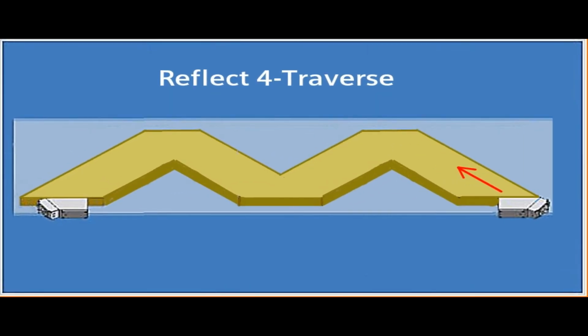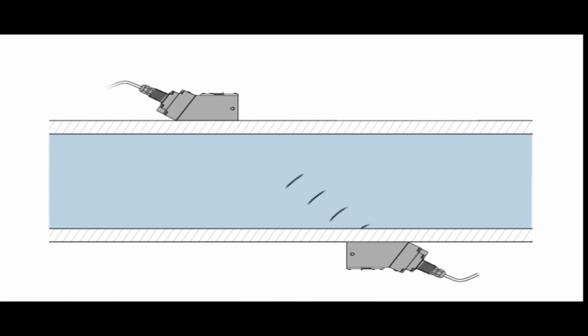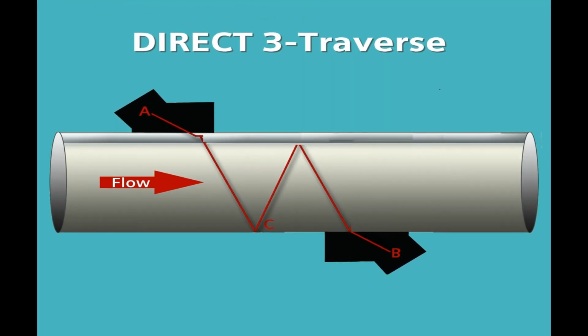4 traverse mounting is only necessary on very small pipes to gain more separation of the flow sensors, or where increased averaging of the flow stream is needed. Direct mounting places one sensor on either side of the pipe. The ultrasonic signal crosses the pipe once, going directly from one sensor to the other, thus only making 1 traverse. There is also a second method of direct mounting known as 3 traverse. This method is rarely used since we could just use reflect.